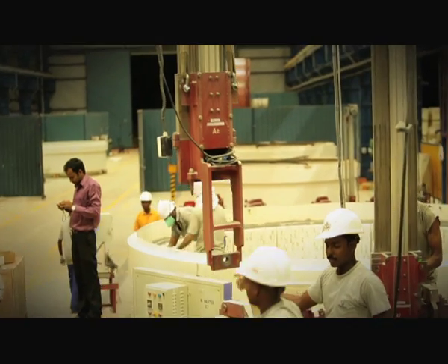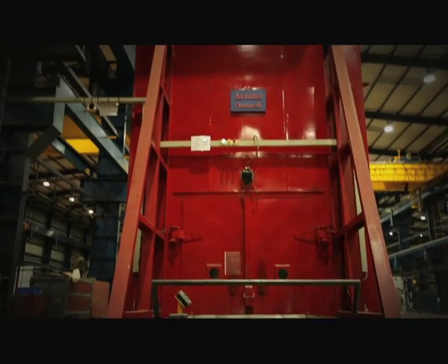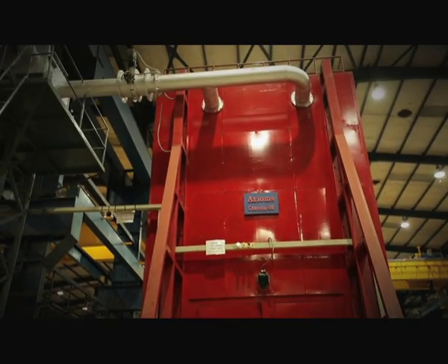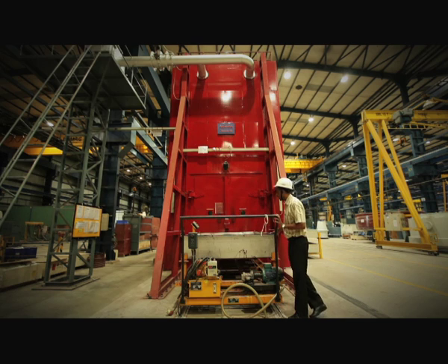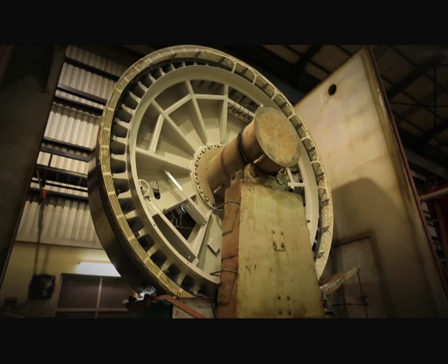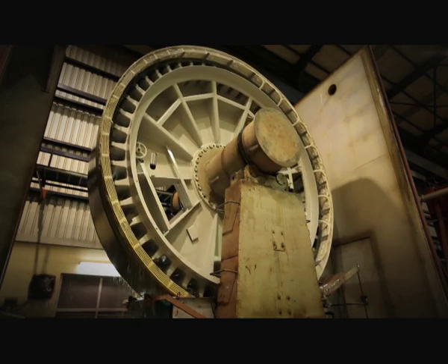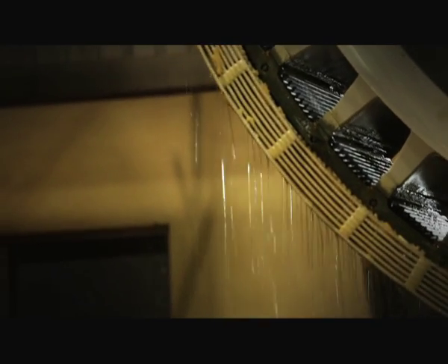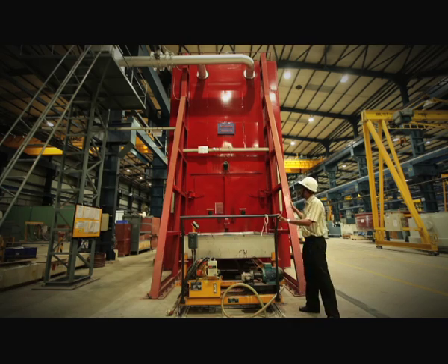This is the impregnation oven. This is the tray where the resin and varnish mixture will be, where the stator will get dipped and heated, and then the cooling cycle goes on. The advantage of this machine is that it is fully automatic. A single person can operate the entire machine.